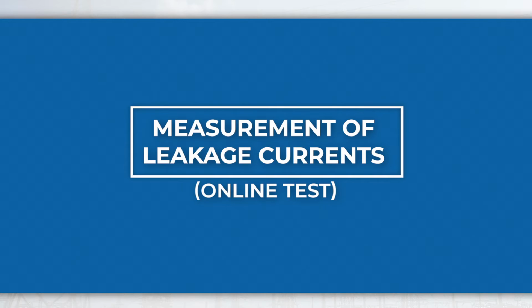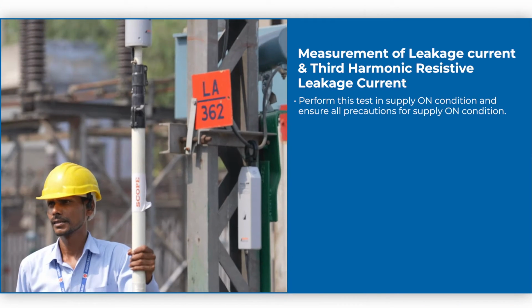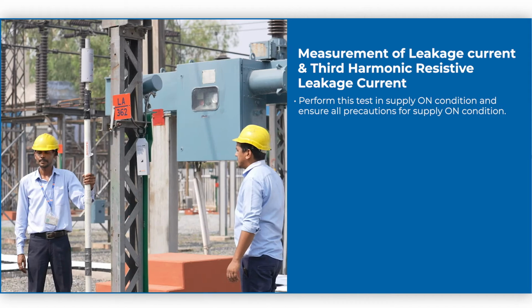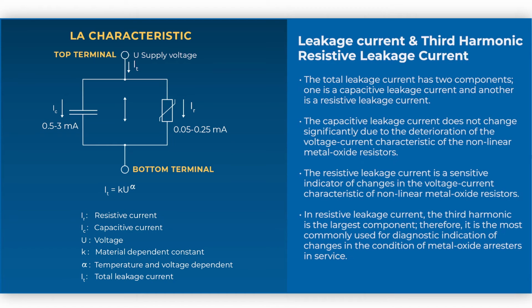Measurement of leakage current. Perform this test in supply on condition and ensure all precautions for supply on condition. The total leakage current has two components. One is a capacitive leakage current and another is a resistive leakage current. The capacitive leakage current does not change significantly due to the deterioration of the voltage current characteristic of the nonlinear metal oxide resistors. The resistive leakage current is a sensitive indicator of changes in the voltage current characteristic of nonlinear metal oxide resistors. In resistive leakage current, the third harmonic is the largest component, therefore, it is the most commonly used for diagnostic indication of changes in the condition of metal oxide arrestors in service.